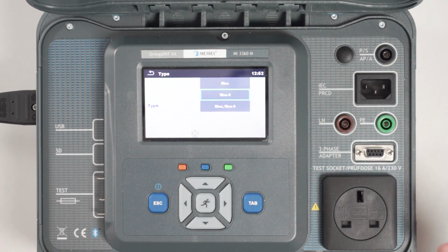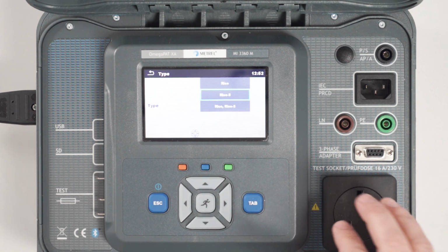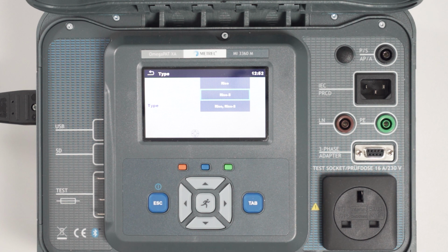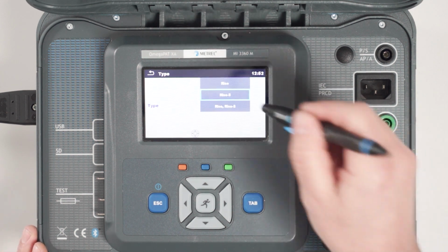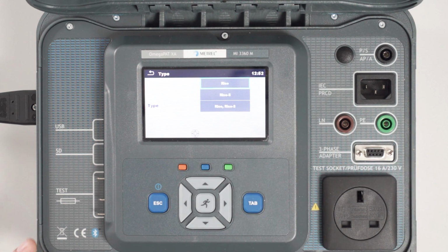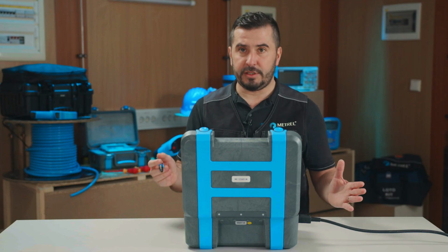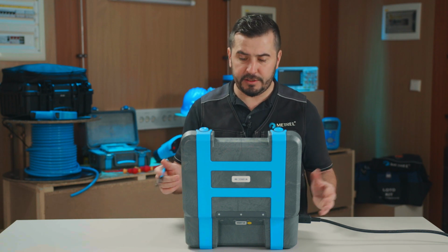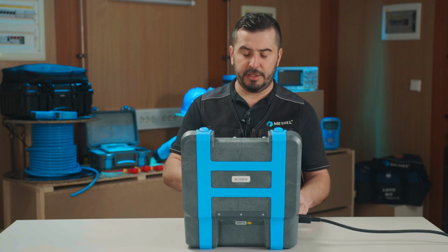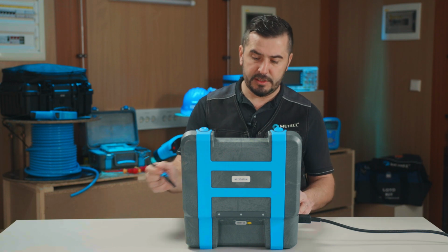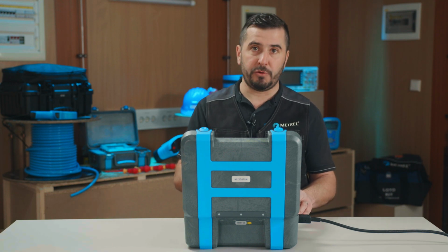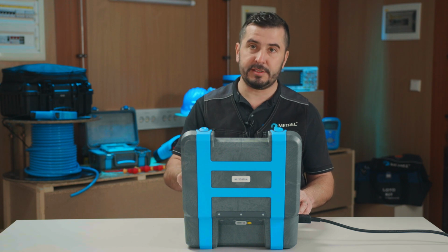So for the insulation resistance, we can measure it either from the test socket itself for class 1 devices, or between live and neutral against the external probe, so we have different options. RISO stands for isolation resistance test, which is being performed from the mains test socket alone. So we don't need any external test lead connected. We simply plug in the device, meaning a class 1 device, and the insulation resistance will be performed between live and neutral in short against the PE.